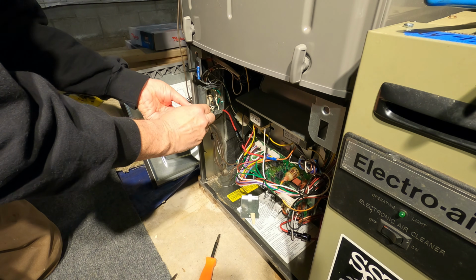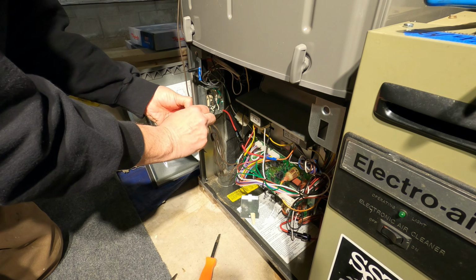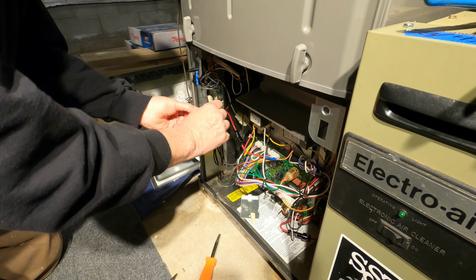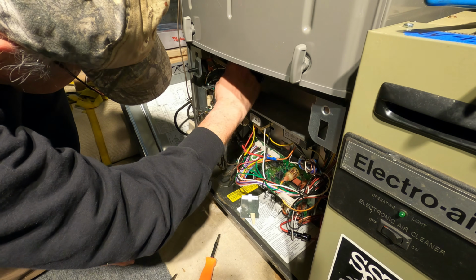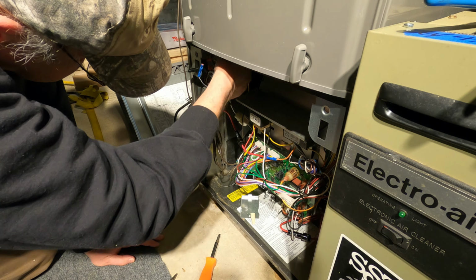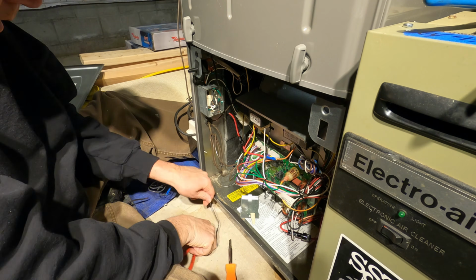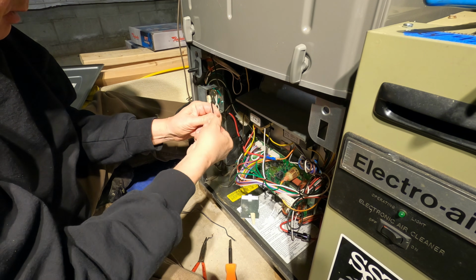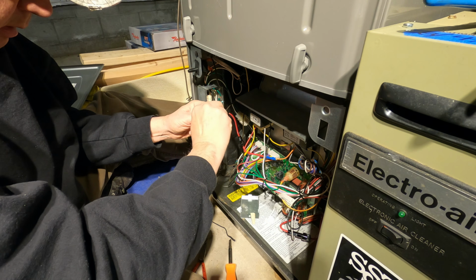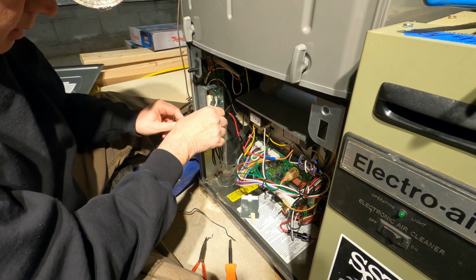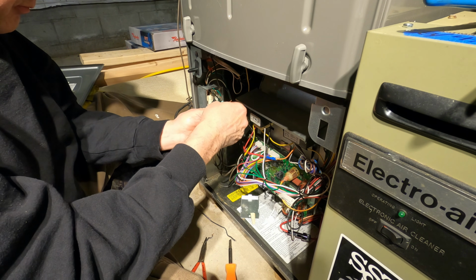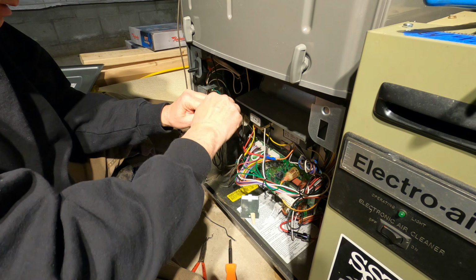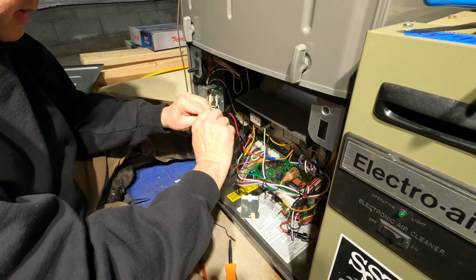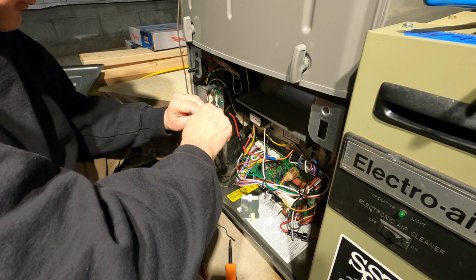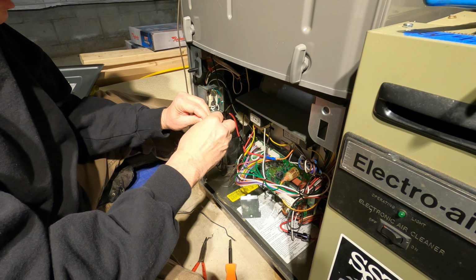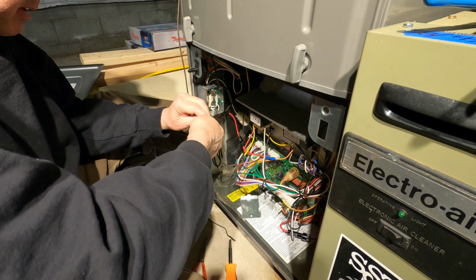The furnace is powered by a 15 amp circuit breaker, so even the safety switch is protected from an overcurrent condition. And so it's okay to take the power for the duct booster through the safety switch, being that it's only 560 milliamps at most. Okay, this is the power conductor coming in from the branch circuit. So this is the power going into the switch.